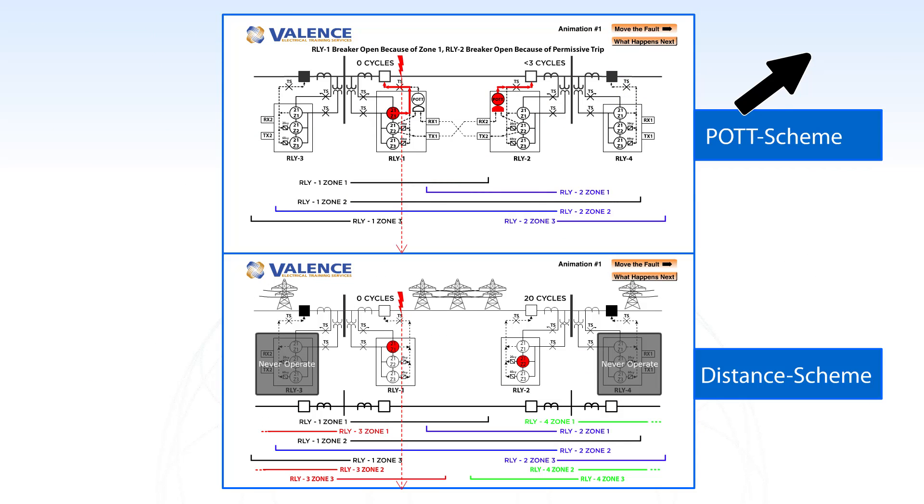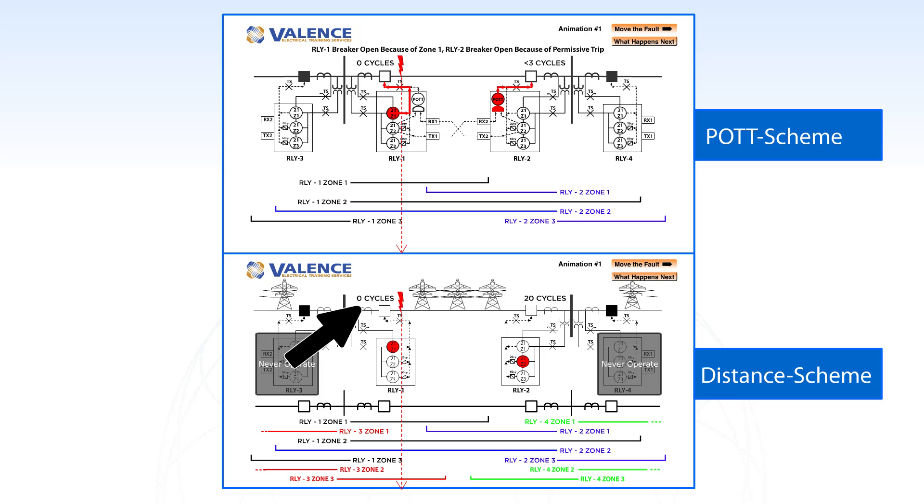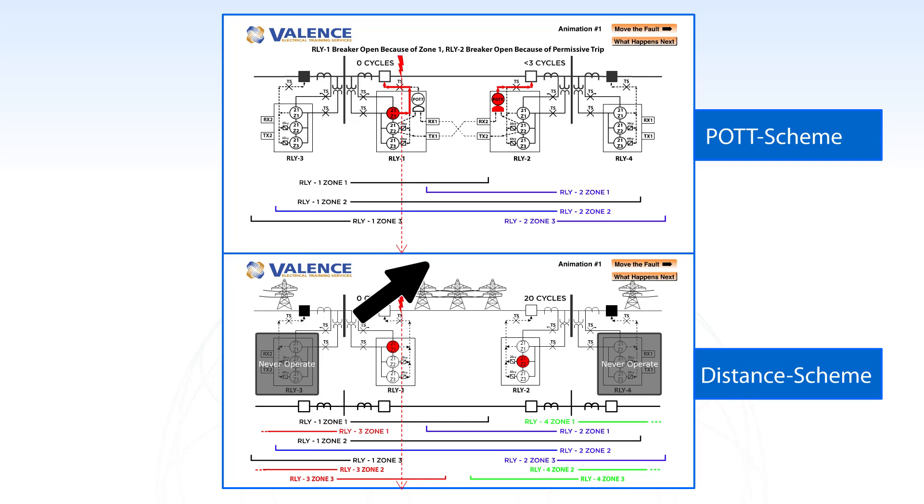When we compare that to what happened with the regular distance protection, the zone 1 of relay 1 operated instantaneously, just like on the communication assisted protection scheme, but the other relay operated in 20 cycles.